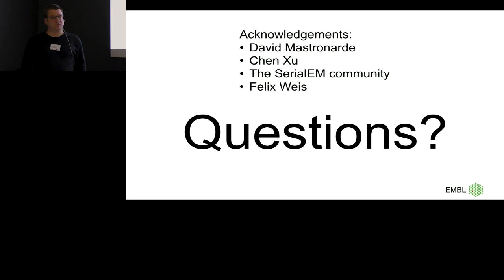Thanks. Very convincing talk. Any questions? About the hardware: who told you that you could have a switch? It's explicitly forbidden by FEI's service department. It's in the manual. But I mean, it causes a ton of problems and certain model switches don't work. The Netgear works. There are also two big switches in the Krios and one was unused, so I'm using that one. You actually ship one in the instrument but explicitly say you cannot use the switch, which is kind of sad because it makes things a lot easier if you have everything hooked up together.